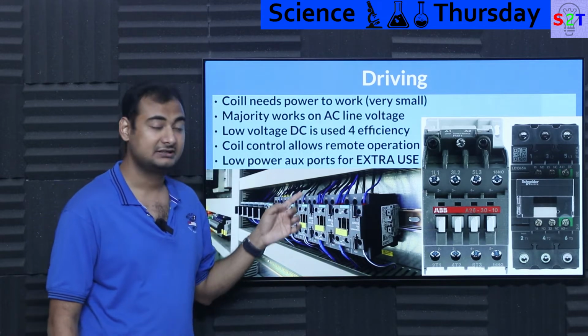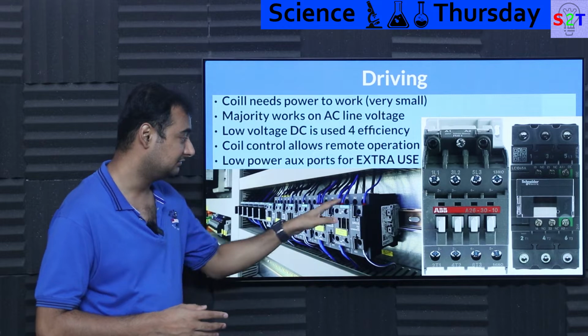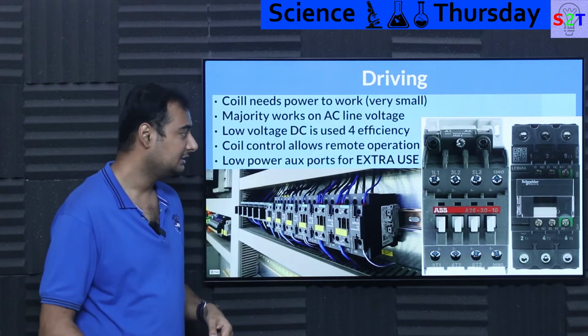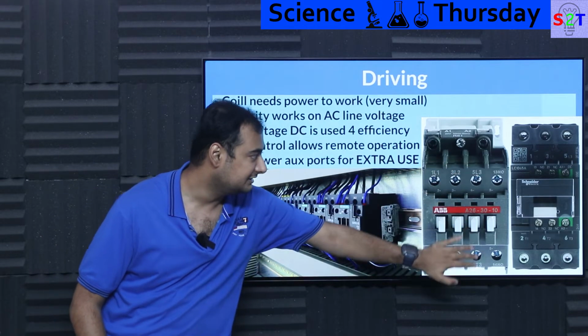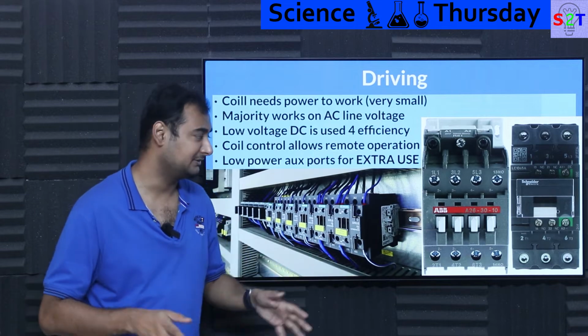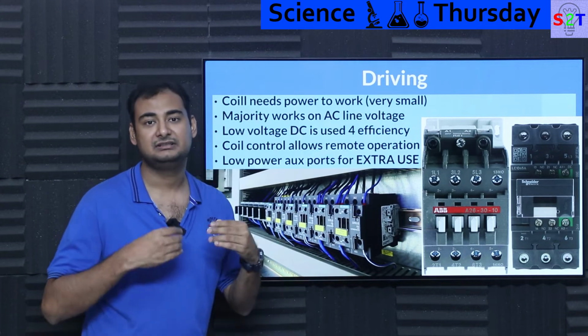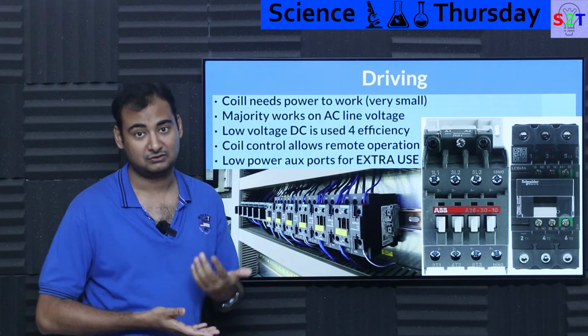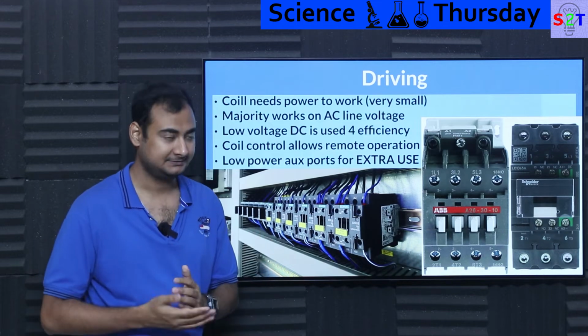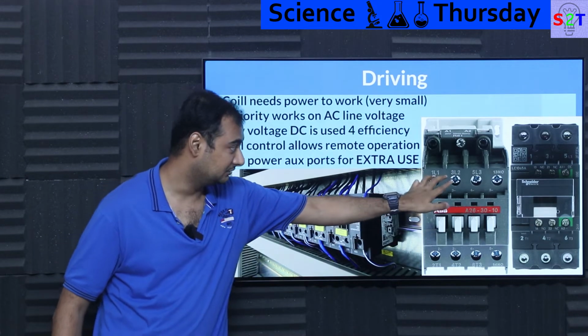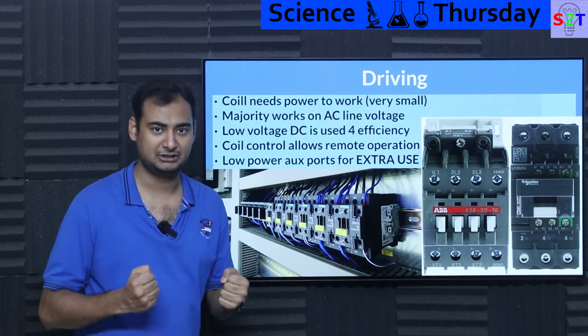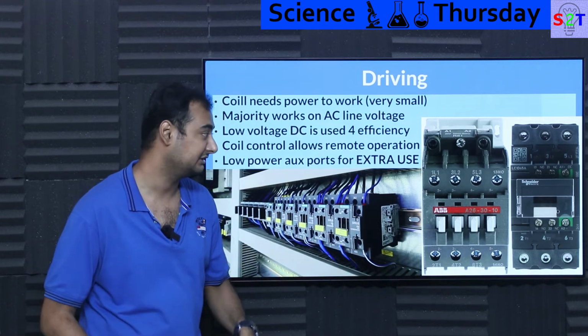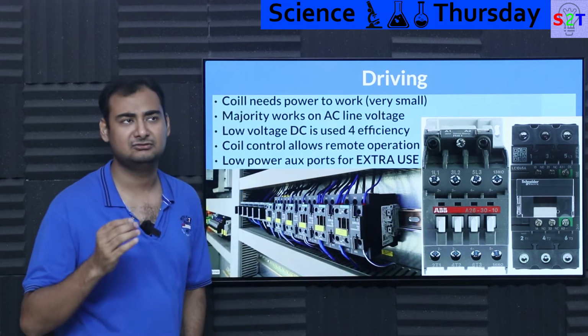Low power auxiliary ports are also added nowadays. You will always have the three main contacts, but also a small one added that will be normally open or normally closed depending on the manufacturer. These are generally for indication lamps, feedback loops, interlocks, those sort of things, not for heavy loads. The three main contacts are designed for the main induction motor inrush current, but that auxiliary side is just a very basic switch.